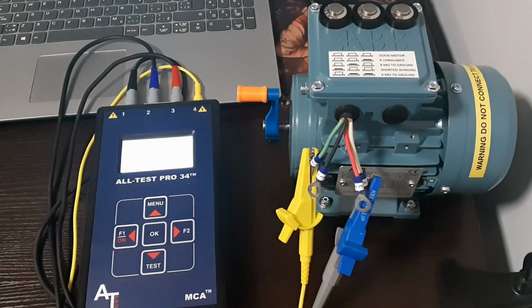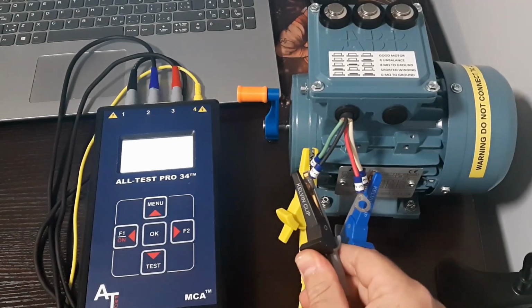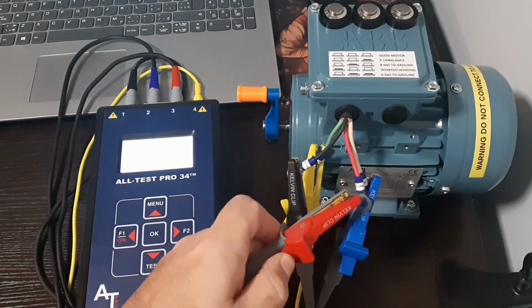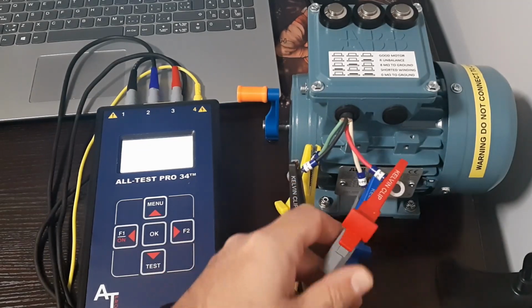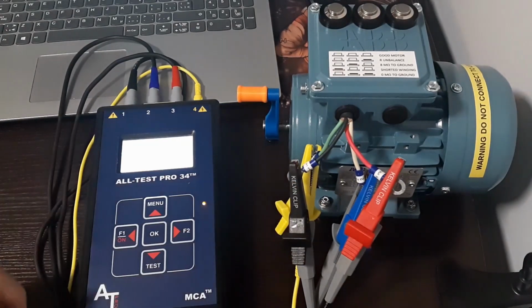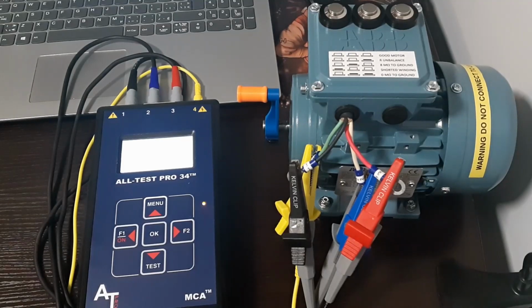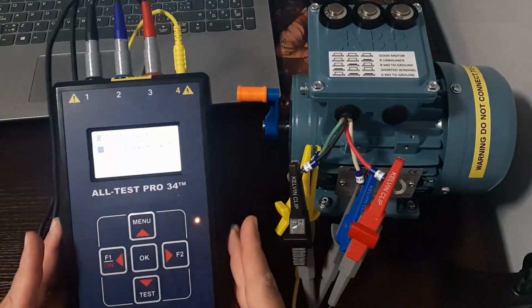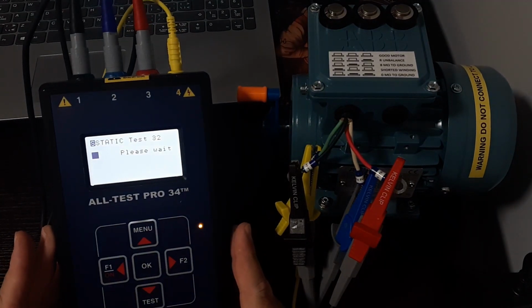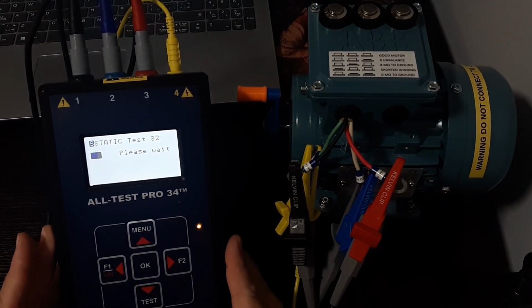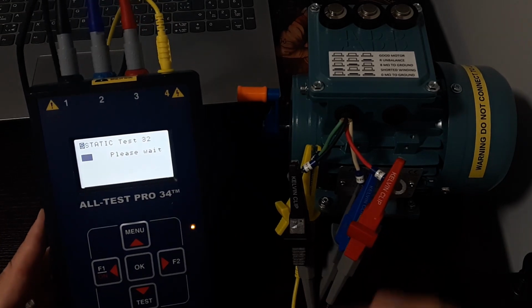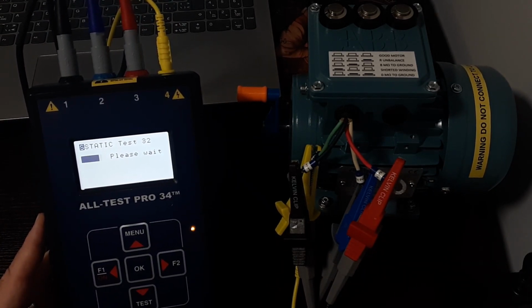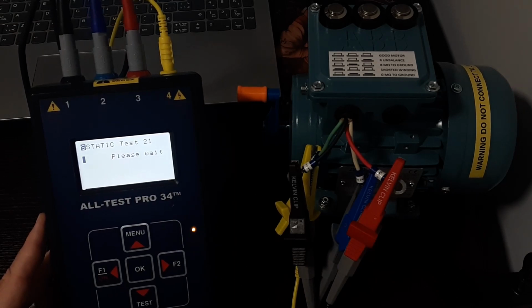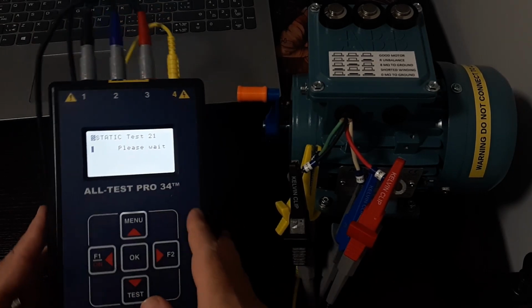It says to connect the black to phase 1 and the red to phase 3. And now it's doing the static test. The static test is automatic. I will tilt this up so we can get a better view here. And it just automatically sends different voltages. It checks the resistance on the phases of the motor. So we get a full test done by that.